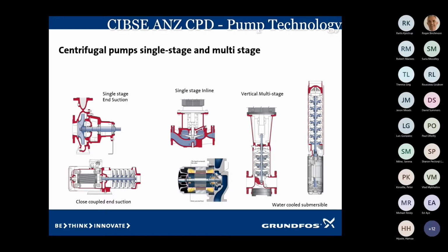The impeller curve, we'll have a look at this a bit later on, but the impeller curve for a single stage pump is quite flat compared to a multi-stage pump. If you look at the vertical multi-stage pump, second to the right there, the water enters into the inlet flange, goes up to the first impeller, then forces water into the second impeller and on into the third impeller. Each time it does that, it adds to its head as it goes through. The curve is very steep and makes it ideal for pressure systems where you're trying to drive variable flow and maintaining a constant pressure.